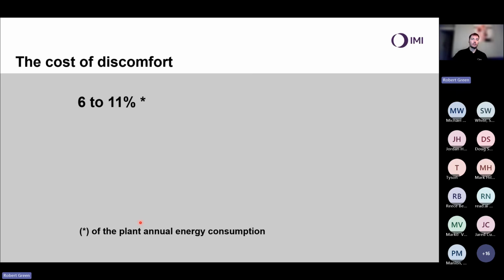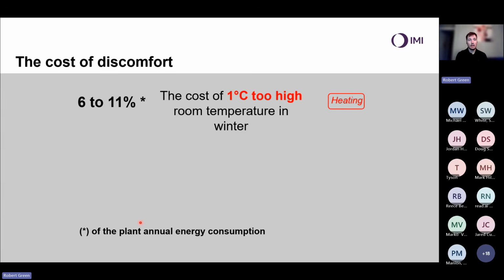And actually, if we look at what we call the cost of discomfort, so often, typically in an unbalanced system, we will lower our set points in cooling, or raise them in heating, because we want to be comfortable. And we say, well, hang on, it's cold in this room, so I'm going to raise my set point. Yes, my set point should be 20 degrees, but I'm going to raise it to 21 degrees. And you can say that's only 1 degree, Rob. It's not a huge amount. But actually, if we take a heating system, we can look at 6 to 11% of additional energy consumption for just 1 degree too high room temperature in winter. So if we've poorly balanced my system, and to compensate for that, we're going to up my set points, we can be looking at running 6 to 11% of additional cost energy consumption in that plant.